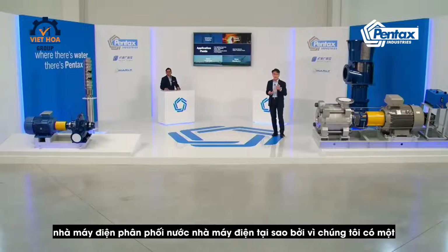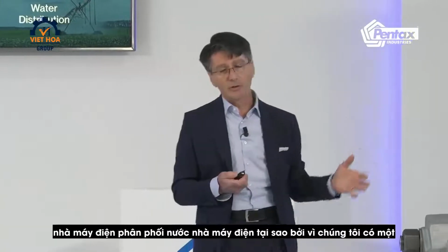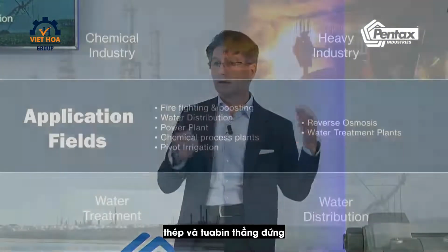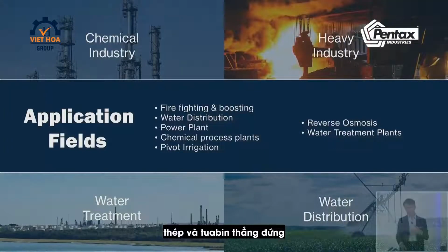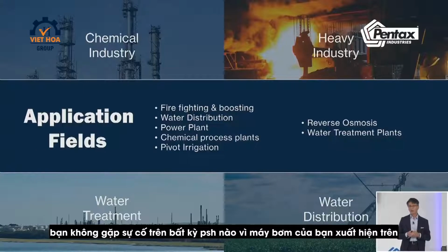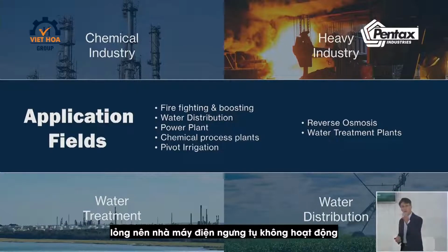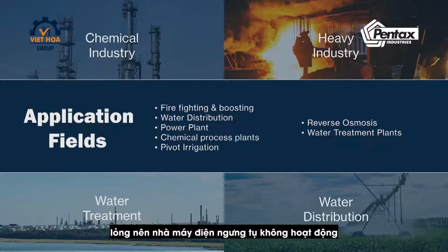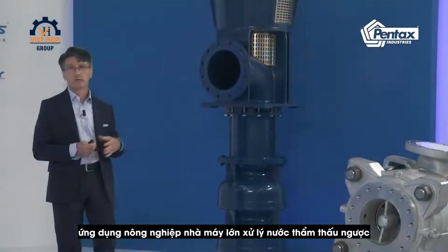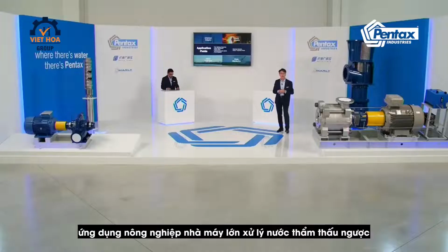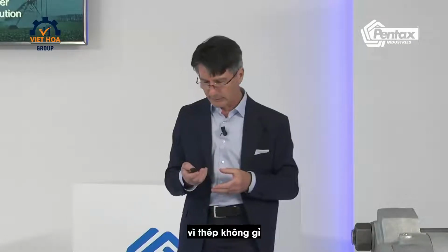Water distribution, power plants. Power plant, why? Because we have stainless steel, and with a vertical turbine, you don't have a problem on NPSH because your pump is immersed in the liquid. So power plant for condensate is ideal. Pivot irrigations, we go back to historical applications, agriculture, large plants. Reverse osmosis water treatment because of the stainless steel.